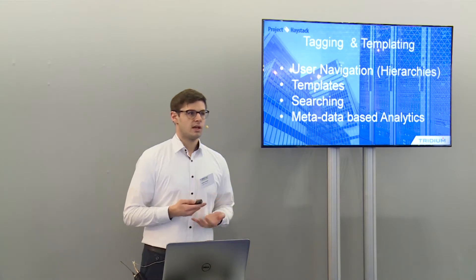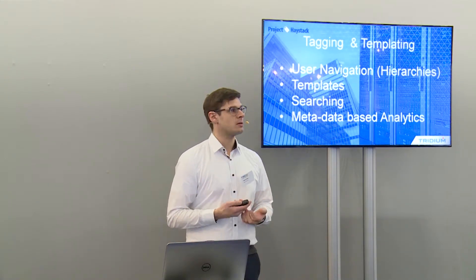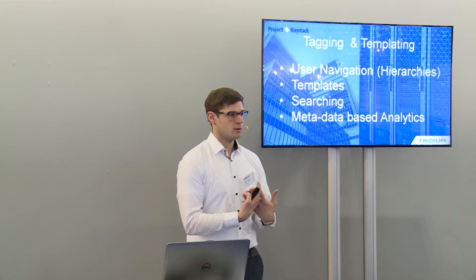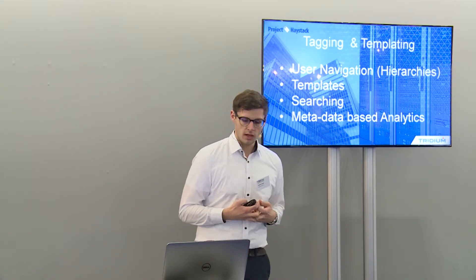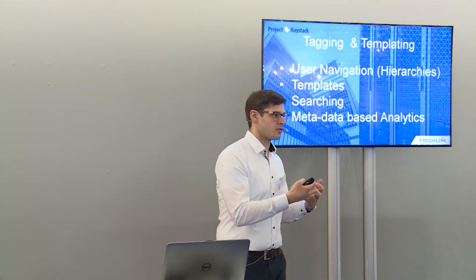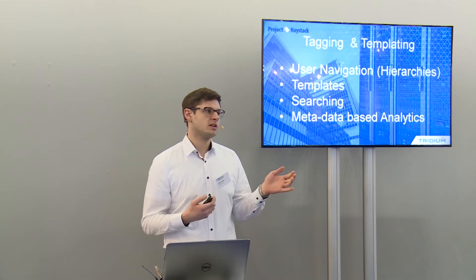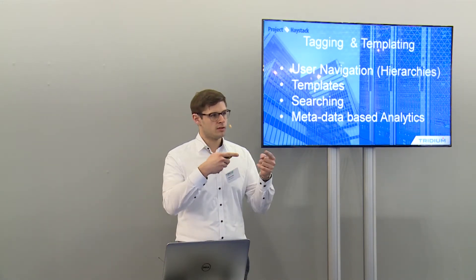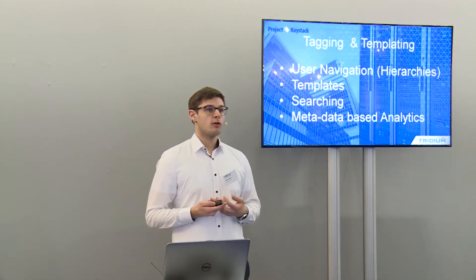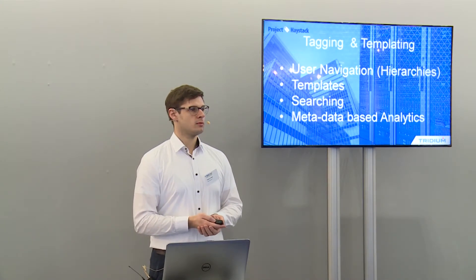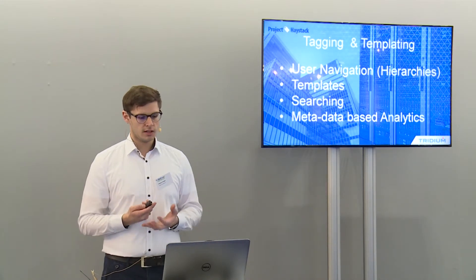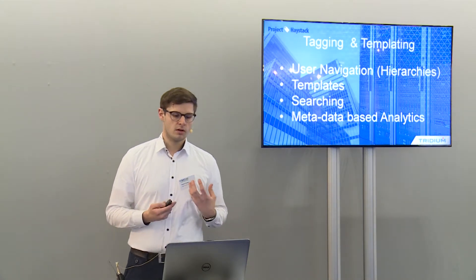We also use tagging and metadata for creating templates, which speeds up engineering significantly. If you're using metadata in the system and you use a template provided by you, a colleague, or your OEM, you just drag and drop the template into the Niagara station and it automatically links to the known inputs and outputs. You can also search your system by metadata, and Niagara analytics algorithms are also based on this metadata.